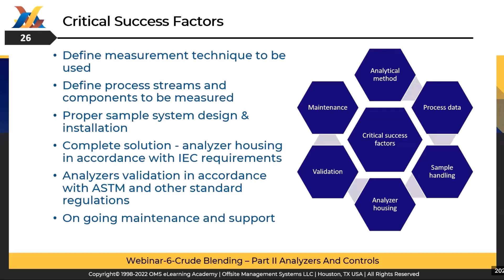Since process analyzer results must be correlated finally against the standard laboratory analysis method, it's essential to select the analytical method from all available techniques correctly. We have also to distinguish between ASTM-based analyzers and correlative analysis technologies. If possible, it's recommended to consider various spectroscopy correlative technologies, which are more reliable and easier to maintain than the others.